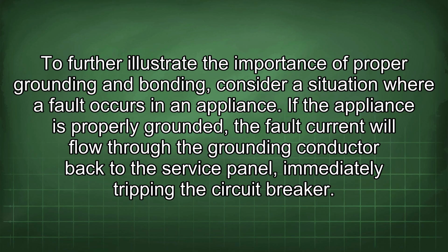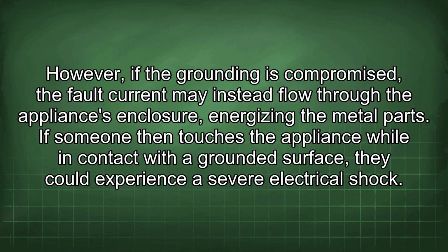To further illustrate the importance of proper grounding and bonding, consider a situation where a fault occurs in an appliance. If the appliance is properly grounded, the fault current will flow through the grounding conductor back to the service panel, immediately tripping the circuit breaker. However, if the grounding is compromised, a fault current may instead flow through the appliance's enclosure, energizing the metal parts. If someone then touches the appliance while in contact with the grounded surface, they could experience a severe electrical shock.